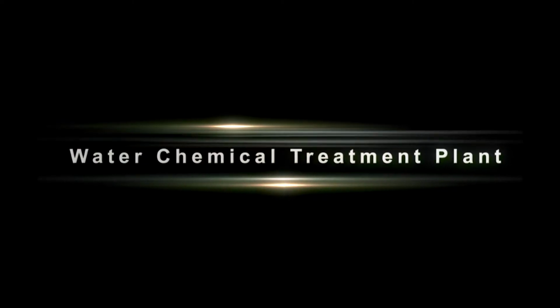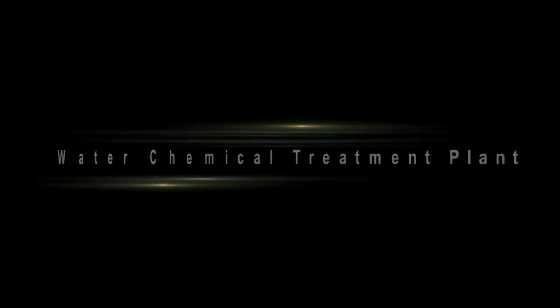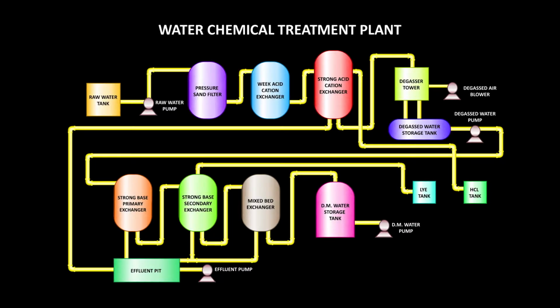Water chemical treatment plant. The borewell water is treated into DM water using ion exchange process. The suspended solid and coloring matters are removed in pressure sand filters. Then the cation filters remove cations like calcium, magnesium, sodium, potassium, etc. in the first stage and the escaped cations in second stage.